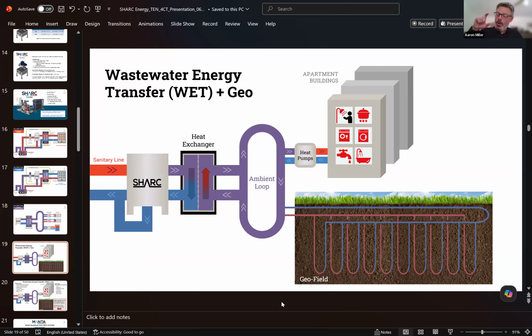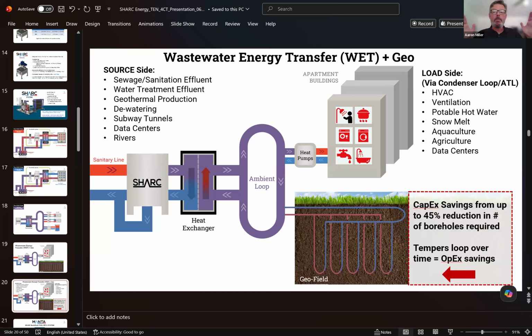So by putting the SHARC into the energy model and using it to pick up the peak cooling loads of those 5 or 6 really hot days, they were able to right size the bore field to pick up just the base cooling load of the building. Think about that. So they were able to go from 128 boreholes down to 90 because that additional capacity was being picked up by the sanitary, the SHARC. So there's real CapEx savings opportunities here where you can potentially short loop your geo loop. As Pete was mentioning before, how many holes do you need?